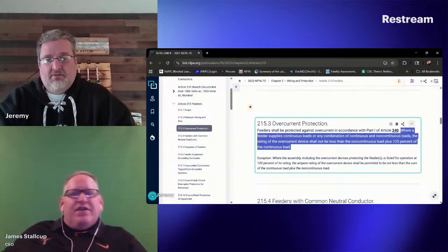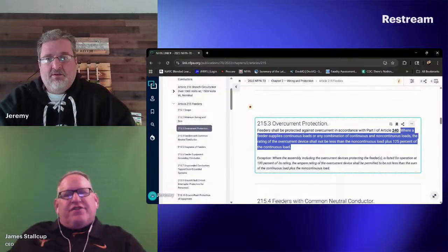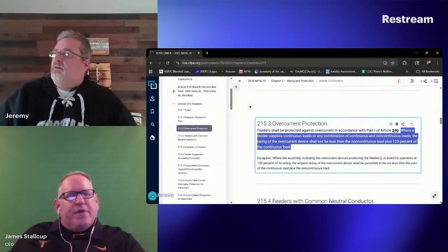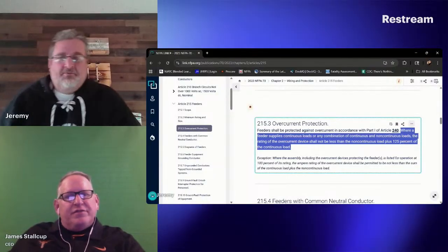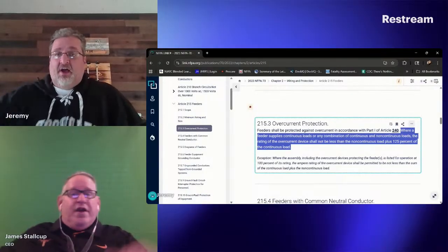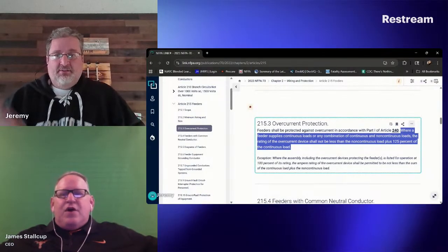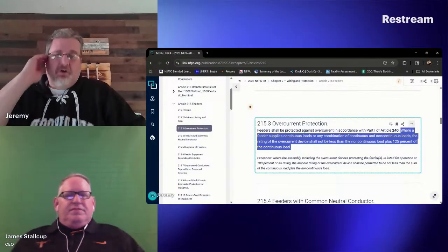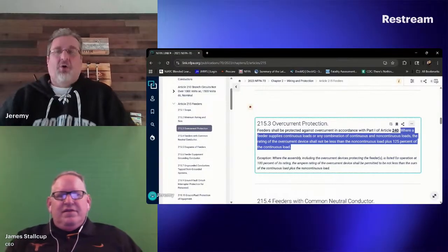It's protecting the load because you sized your conductors. And if you look at 240.4, that's a protection of your conductors when you size your overcurrent device, and it tells you to look at 240.4A through H. 240.4 doesn't care how you got your conductor. Well, I don't even know why they put overcurrent protection in there then. 240.4 has nothing to do with protecting a load.